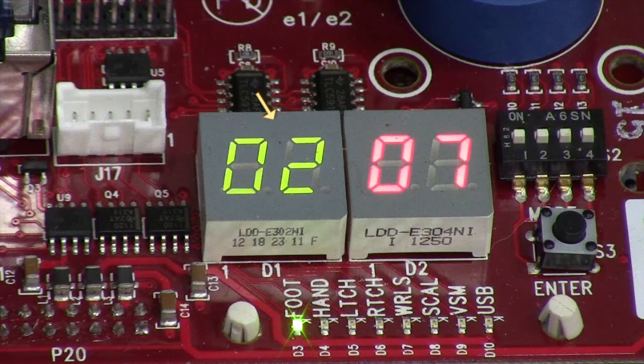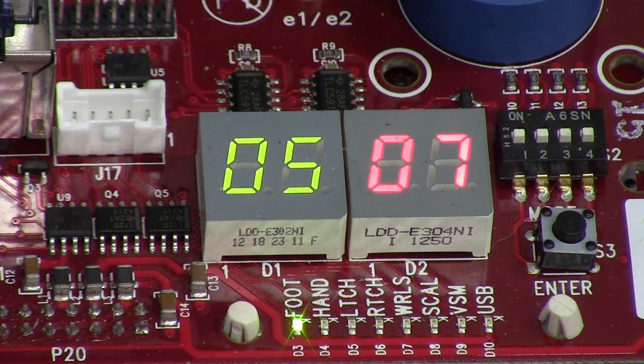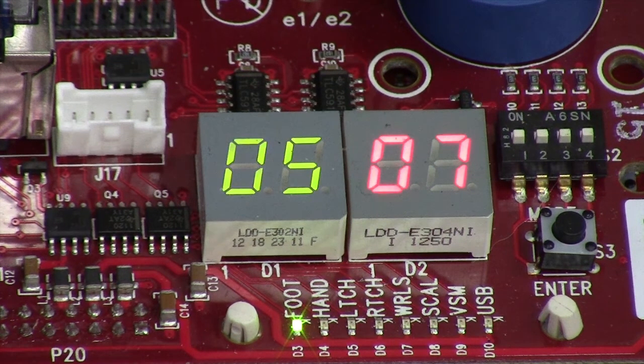The ID code, which is the green display, indicates the function or system where the problem occurs. For example, 02 indicates base, 04 indicates tilt, and 05 indicates foot. More than one ID code may be displayed if more than one function or system is affected.